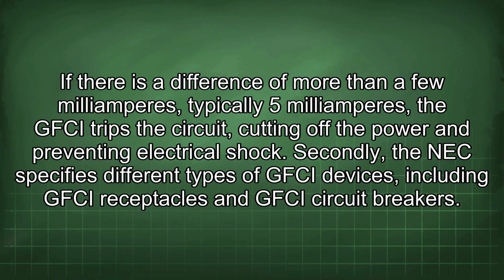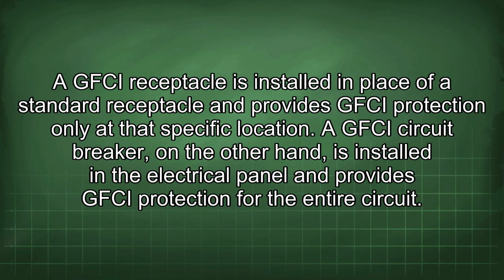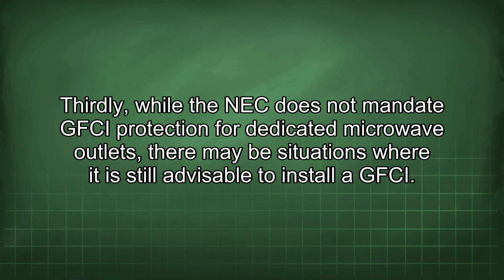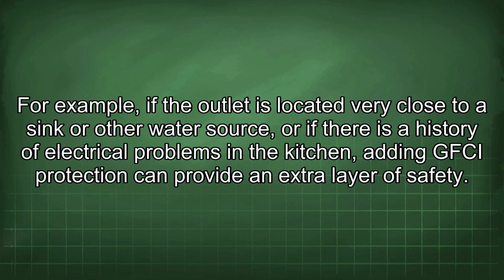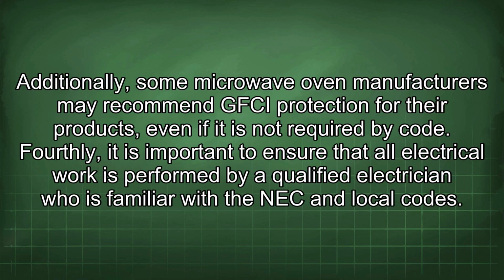Secondly, the NEC specifies different types of GFCI devices, including GFCI receptacles and GFCI circuit breakers. A GFCI receptacle is installed in place of a standard receptacle and provides GFCI protection only at that specific location. A GFCI circuit breaker, on the other hand, is installed in the electrical panel and provides GFCI protection for the entire circuit. Thirdly, while the NEC does not mandate GFCI protection for dedicated microwave outlets, there may be situations where it is still advisable to install a GFCI. For example, if the outlet is located very close to a sink or other water source, or if there is a history of electrical problems in the kitchen, adding GFCI protection can provide an extra layer of safety. Additionally, some microwave oven manufacturers may recommend GFCI protection for their products, even if it is not required by code.